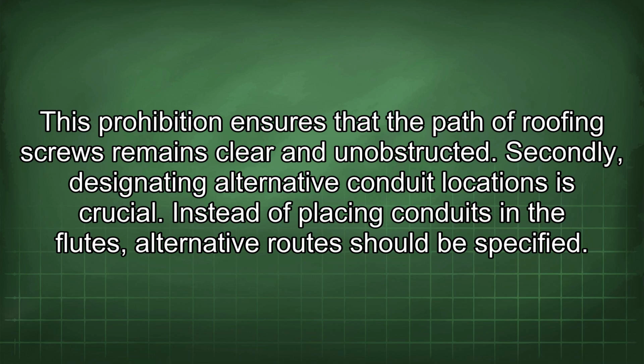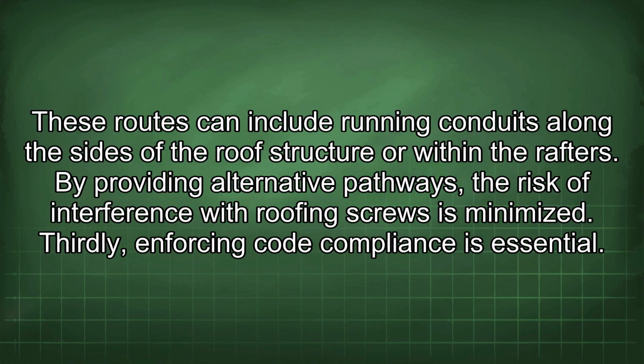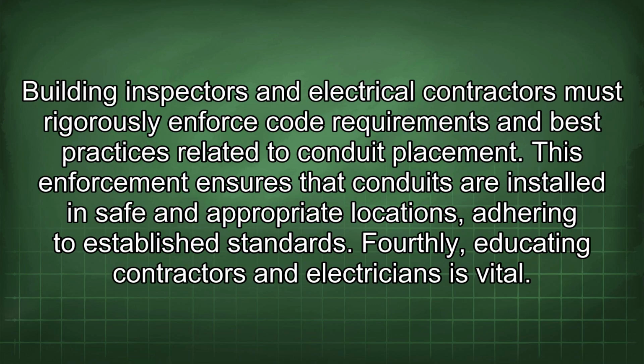Secondly, designating alternative conduit locations is crucial. Instead of placing conduits in the flutes, alternative routes should be specified. These routes can include running conduits along the sides of the roof structure or within the rafters. By providing alternative pathways, the risk of interference with roofing screws is minimized. Thirdly, enforcing code compliance is essential. Building inspectors and electrical contractors must rigorously enforce code requirements and best practices related to conduit placement. This enforcement ensures that conduits are installed in safe and appropriate locations, adhering to established standards.